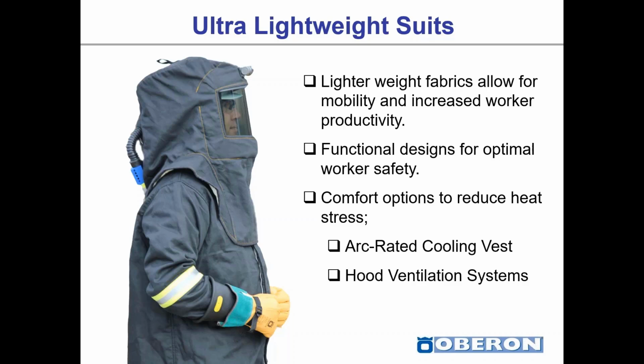Such as an arc-rated cooling vest that you could wear underneath the suit or over top of your daily wear. The ventilation systems. This image here shows the side shot of me wearing an arc flash suit. You can see the hose at the back, which is that small little fan unit that brings external air inside the hood, and then that air is diverted up and around and down the inside of the lens. The purpose of this is to deliver the air to the breathing zone for the worker to be comfortable. We want a gentle flow of air that's delivered right to where they need it, right where their breathing zone is.